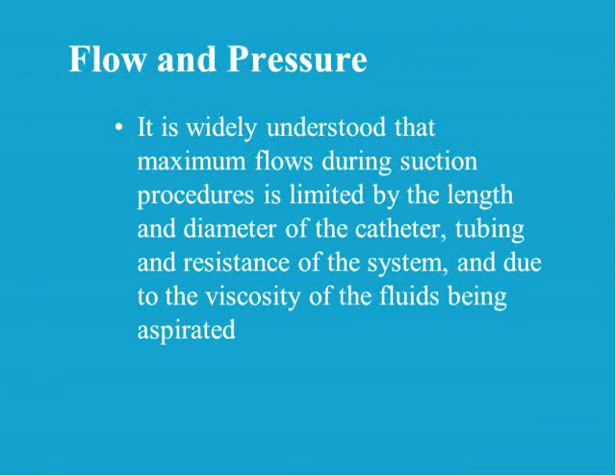This is a study that was done by Pursley. What he was looking at is variation. Although there might be different flow rates coming off the vacuum regulator by one regulator versus another, the flow at the patient, measured at the end of a 12 French suction catheter, is pretty flat. In other words, there are slight variations, but there's no clinical significance in how much flow you're actually going to get at the patient. So higher flow at the vacuum regulator doesn't really mean anything as far as what you're going to get at the patient.